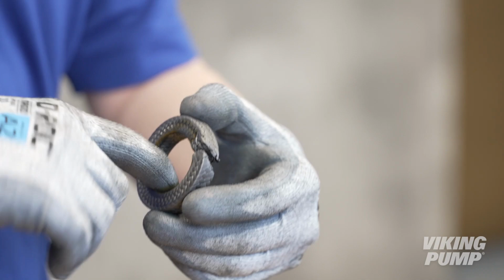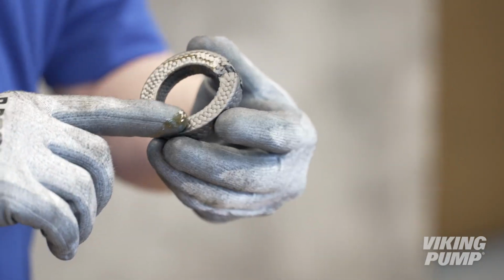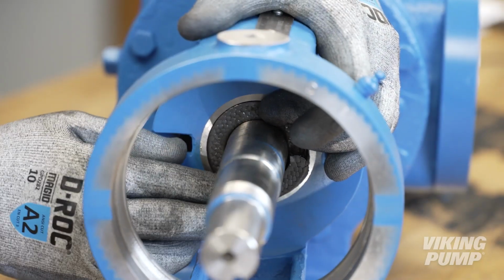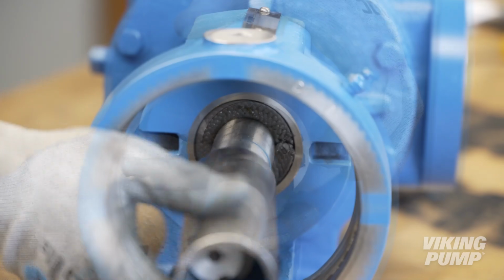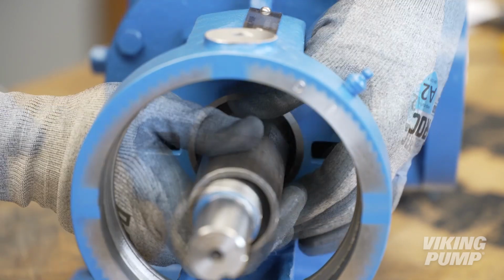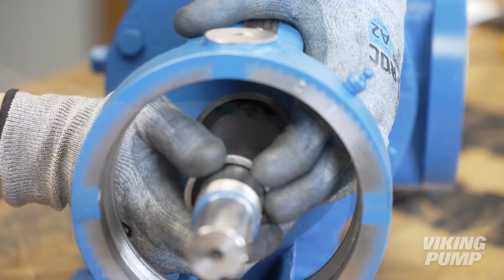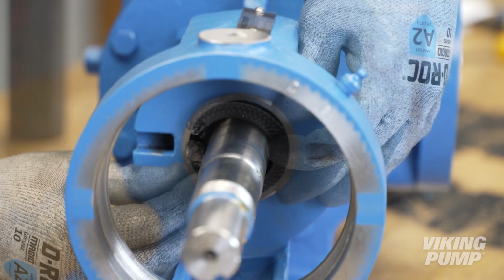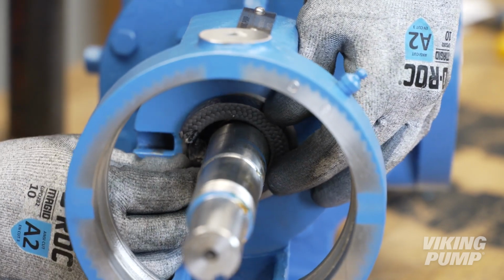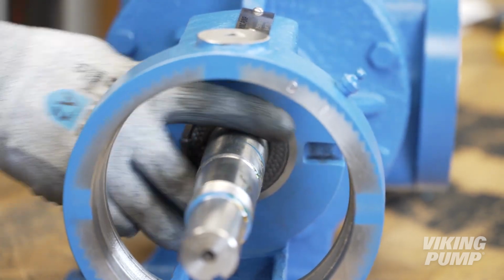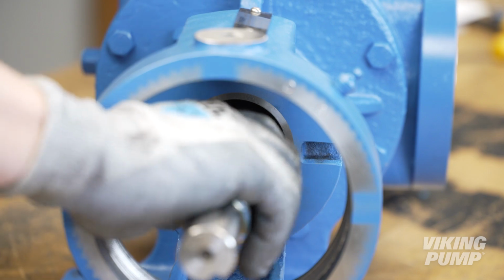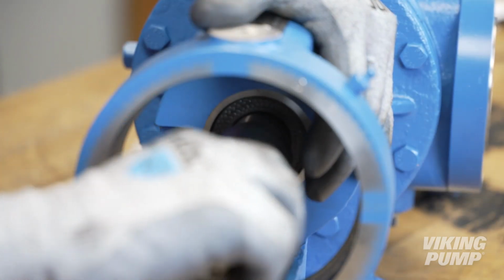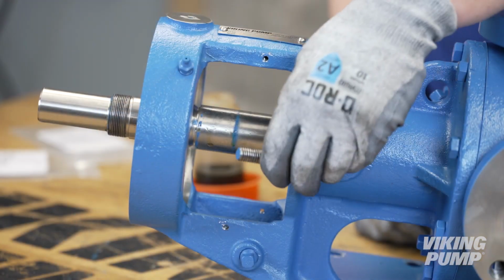Install the packing. Lubricate each packing ring and install. Fully set each ring with a length of pipe. Make sure to alternate the packing ring joints from one side of the shaft to the other. When the packing is installed, install the T-bolts.